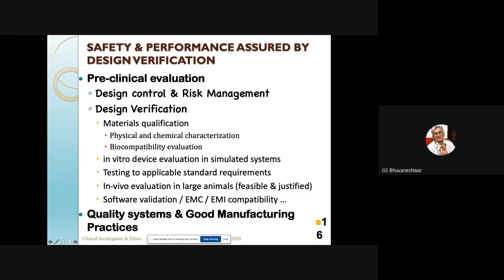Then your software has to be validated properly before you get into clinical studies. As I said, EMI, EMC compatibility. Then other thing you need to do is when your quality systems as per ISO 13485 and good manufacturing practices should be implemented for the batch of devices that you're going to make for the clinical studies.